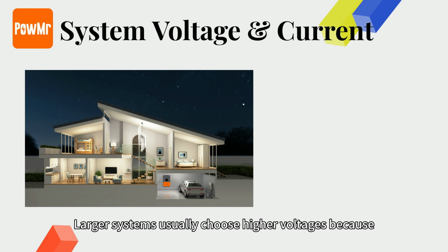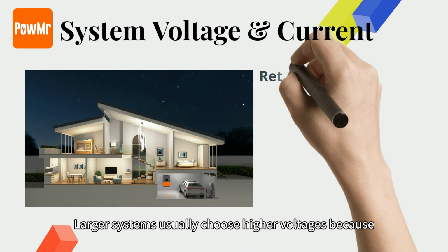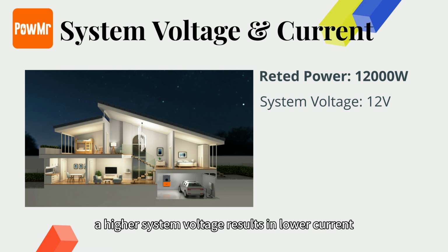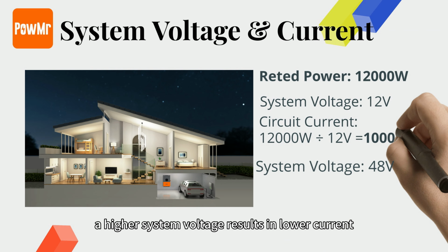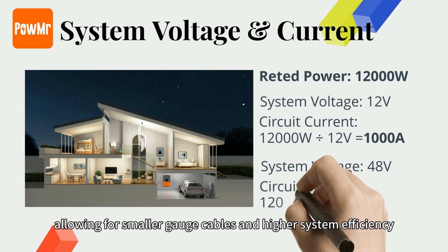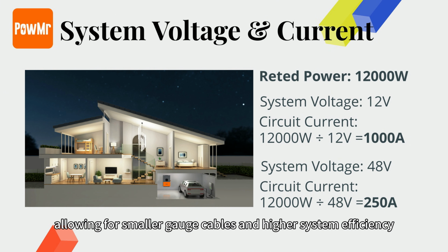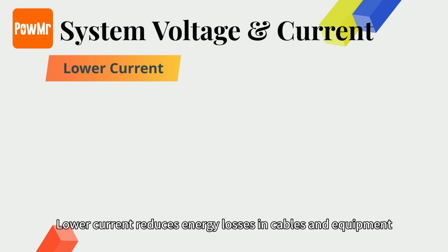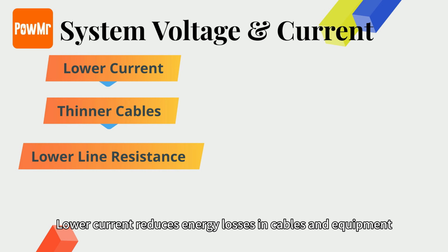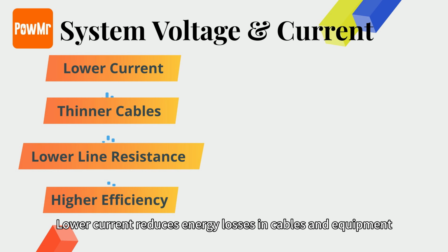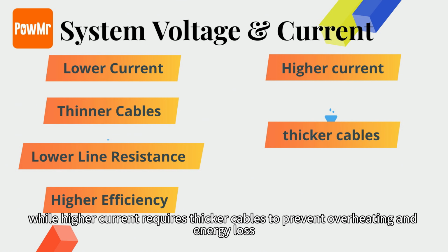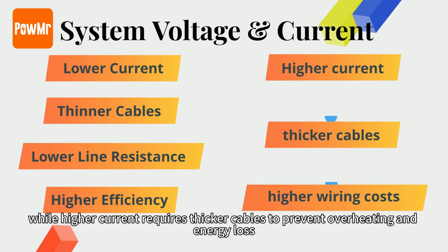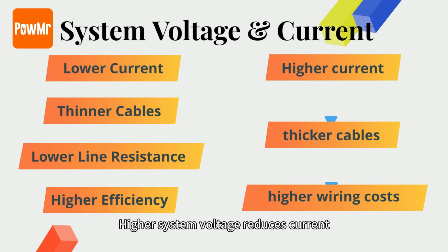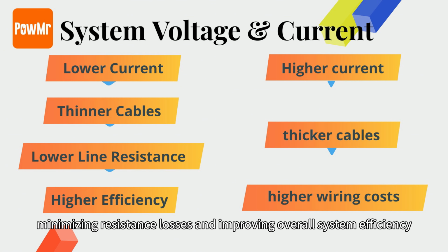Larger systems usually choose higher voltages because at the same power level, the higher system voltage results in lower current, allowing for smaller gauge cables and higher system efficiency. Lower current reduces energy losses in cables and equipment, while higher current requires thicker cables to prevent overheating and energy loss. Higher system voltage reduces current, minimizing resistance losses and improving overall system efficiency.